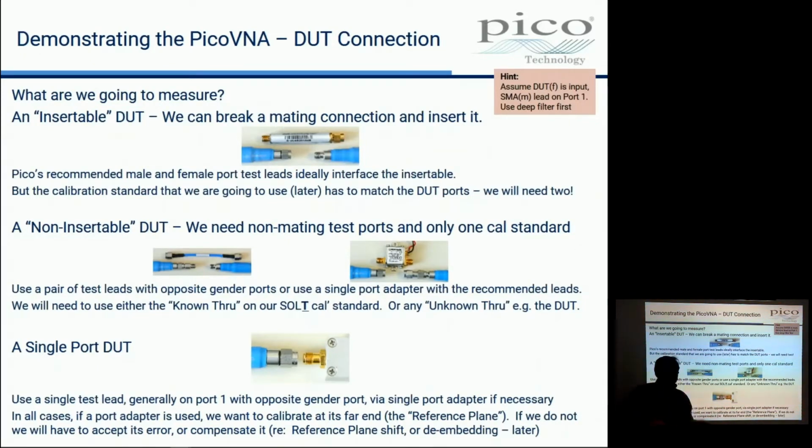So we're going to now prepare for our demonstration. Let's first talk about the things we can measure, and we need to talk about them in the form of an insertable DUT or a non-insertable DUT.